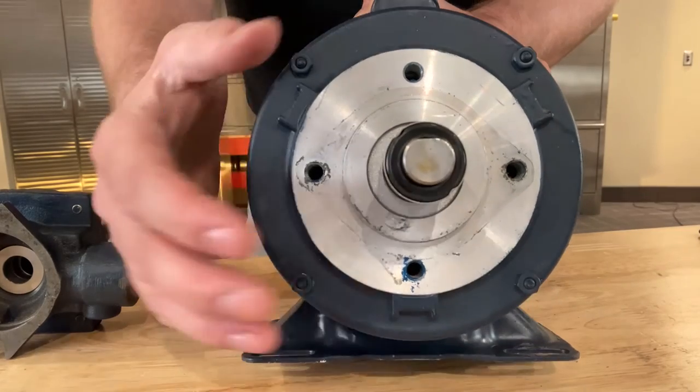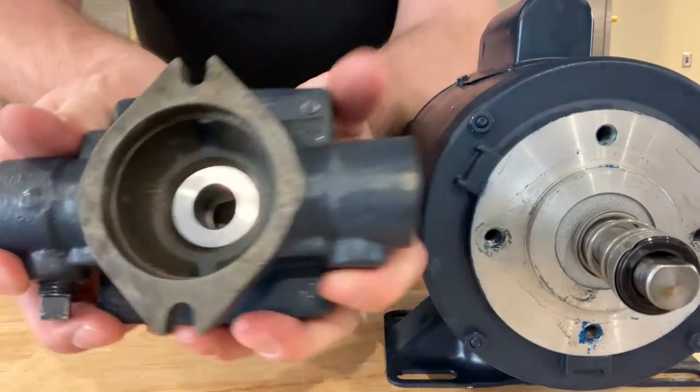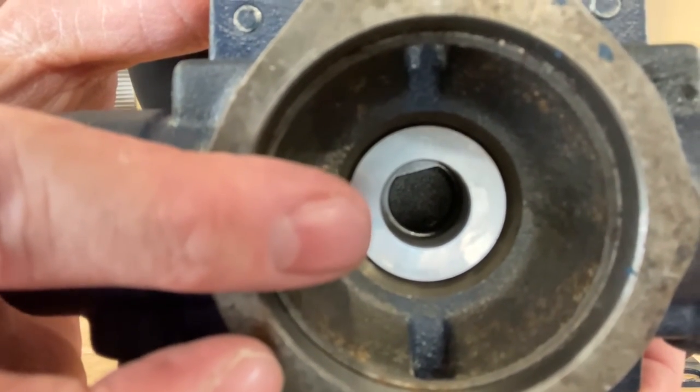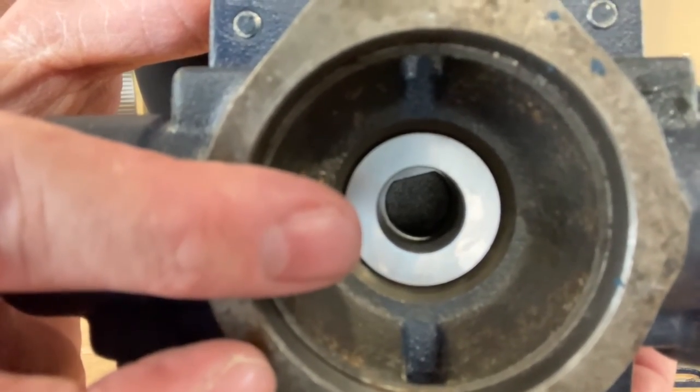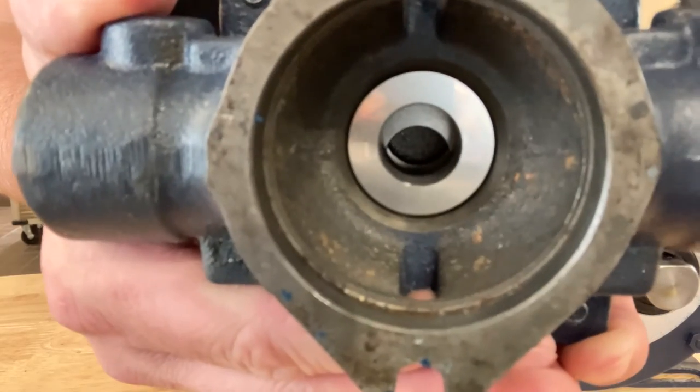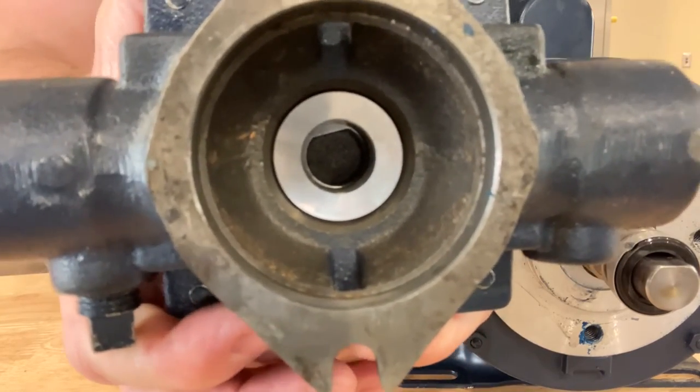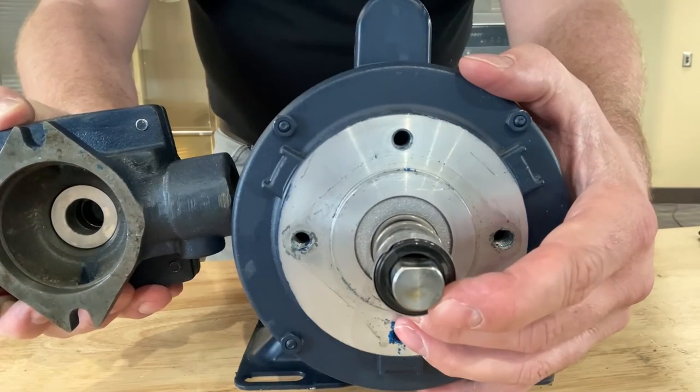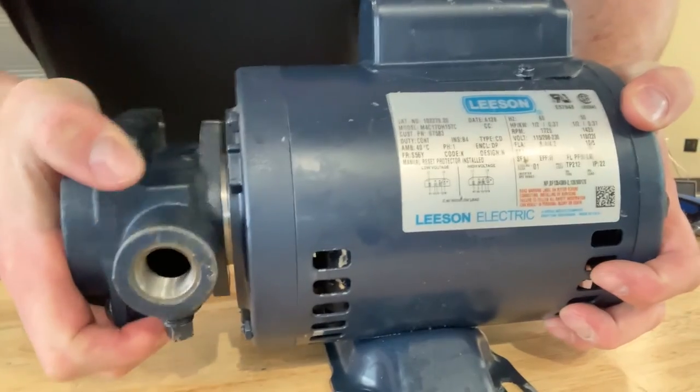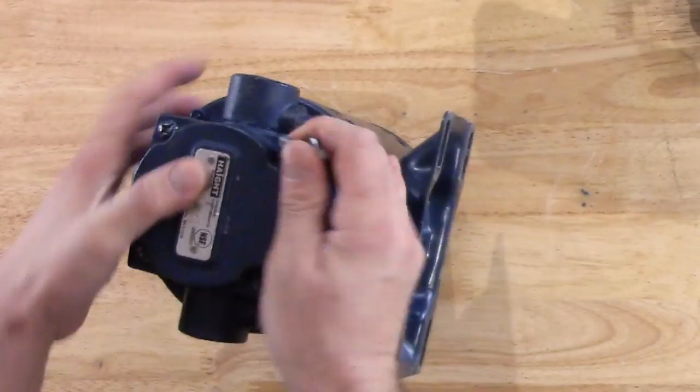When going back together, it's important to notice that the shaft on the motor is D-shaped. This is important to note in the orientation of the shaft, because just like the shaft is D-shaped, so is the impeller inside of our pump cavity. You can see if I have the pump in this rotation, that it sits up perfectly in center with the inside of the pump cavity. If I turn the pump cavity 180 degrees, you can see that it's no longer in the center. So it's important to have the pump cavity in this orientation so that the rotor, you can see the D-shape, and now we can line our D-shape up on our shaft accordingly so that when we go back together, this will make this process much easier in terms of lining up. Now that we have that pushed on, we can start our upper flange bolt. Now we can flip it up and get our other flange bolt in.